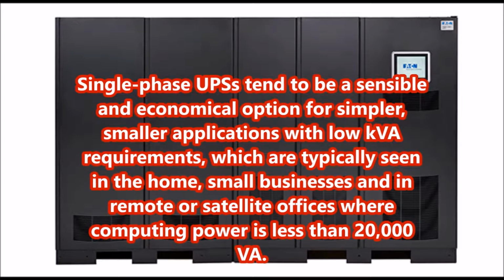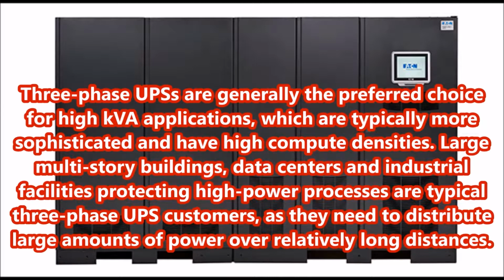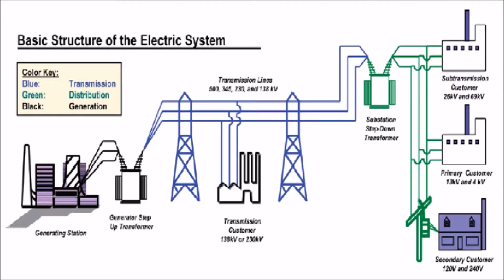Single-phase UPSs tend to be a sensible and economical option for simpler, smaller applications with low kVA requirements, which are typically seen in the home, small businesses and in remote or satellite offices where computing power is less than 20,000 VA. Three-phase UPSs are generally the preferred choice for high kVA applications, which are typically more sophisticated and have high compute densities. Large multi-story buildings, data centers and industrial facilities protecting high-power processes are typical three-phase UPS customers, as they need to distribute large amounts of power over relatively long distances. In the shown figure, the three-phase power is generated and distributed to large commercial customers, with secondary customers, like homeowners, only receiving single-phase power.